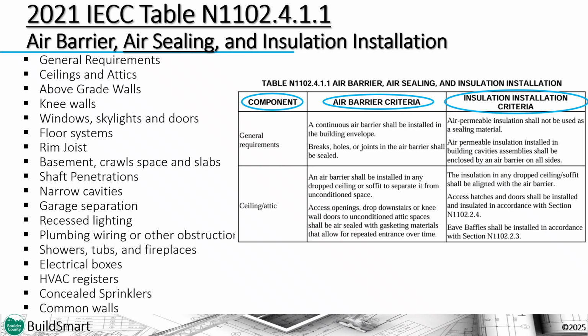There are 19 components of the building thermal envelope that are addressed by the air barrier, air sealing, and insulation installation table N1102.4.1.1. They are addressed from an air barrier, air sealing perspective, as well as from an insulation installation perspective. I can't address all the components, but know that the requirements are different than in the base 2021 IECC. In general, the table should be approached by thinking about the specific component, but also how the techniques that are described can be applied to other like assemblies that are not specifically called out.